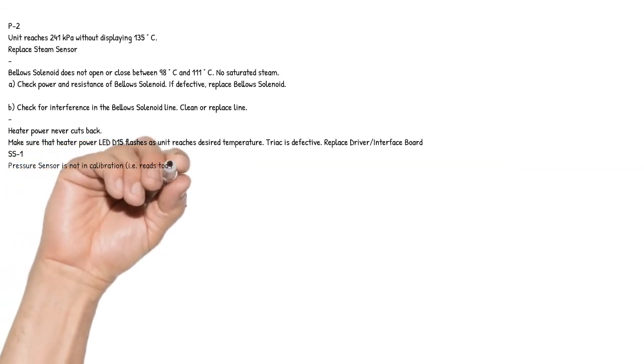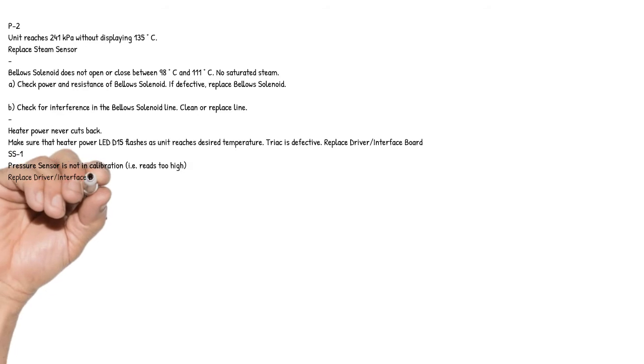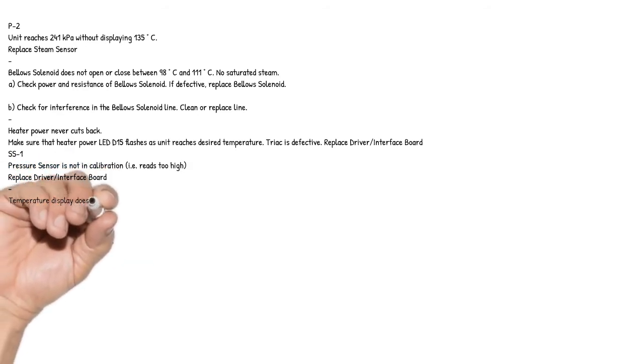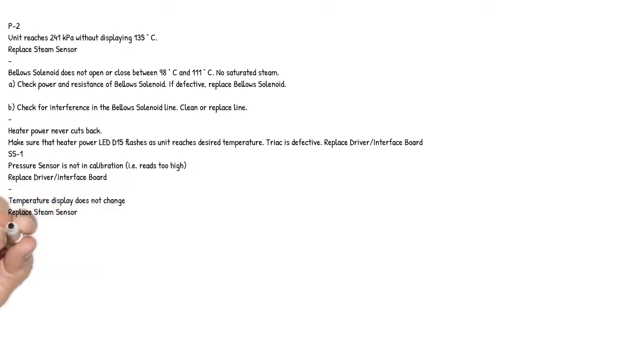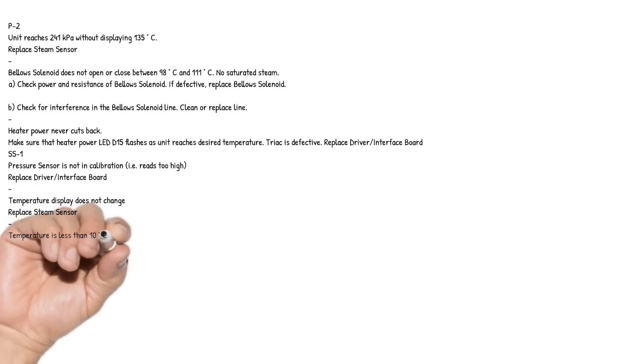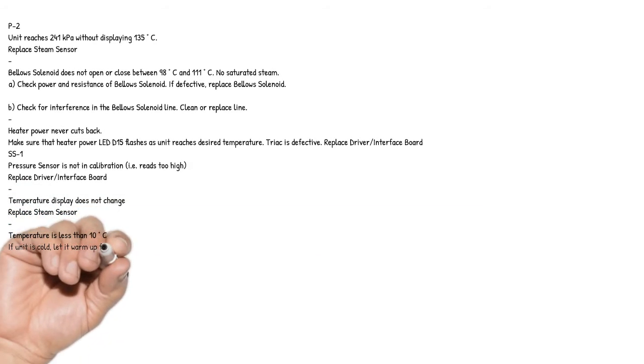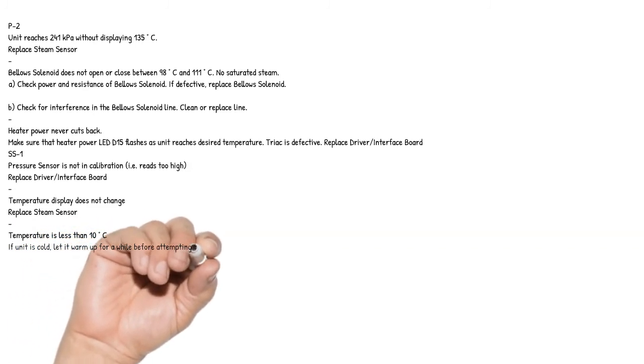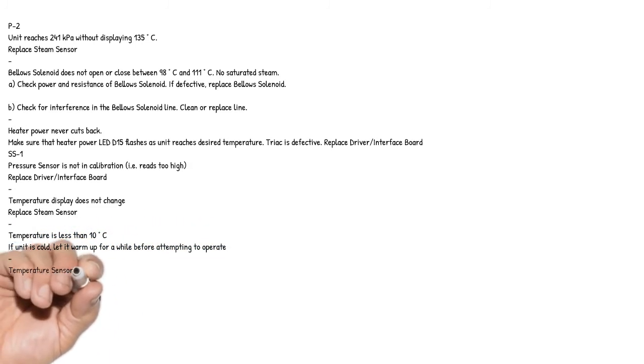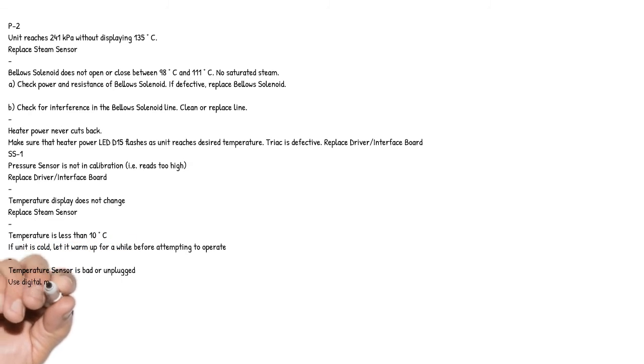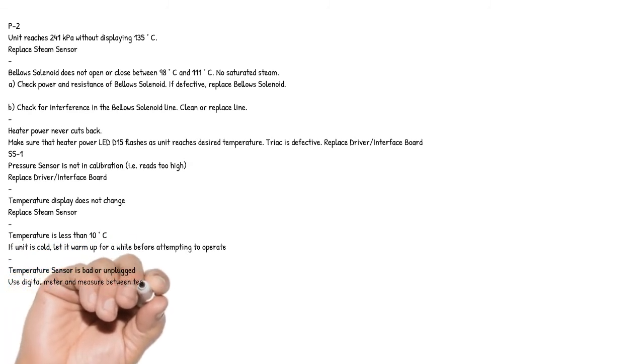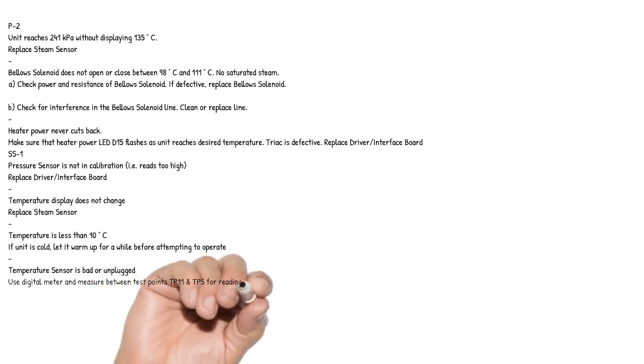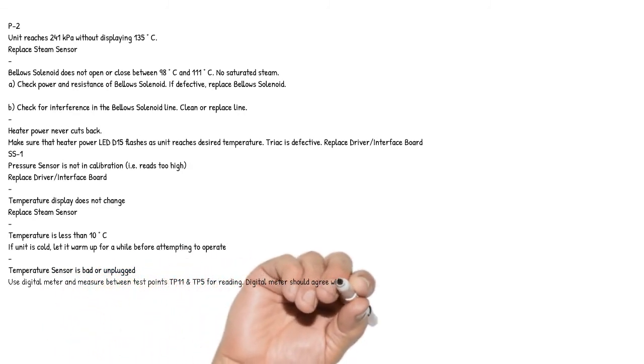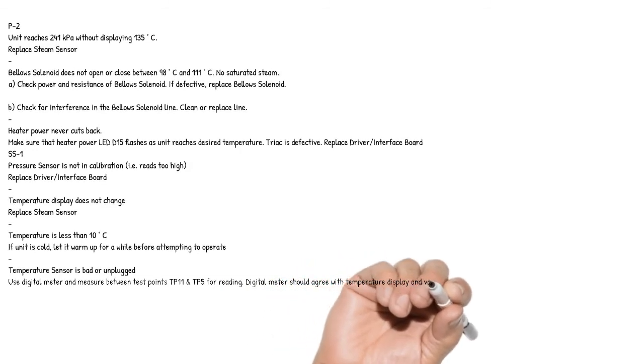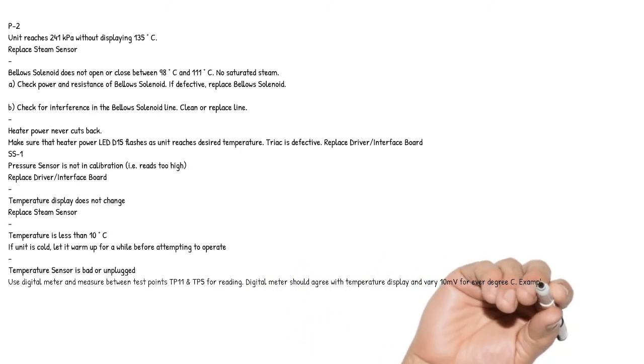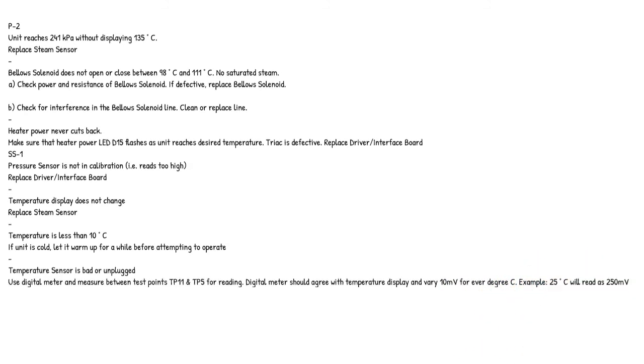SS1. Pressure sensor is not in calibration, i.e. reads too high. Replace driver/interface board. Temperature display does not change. Replace steam sensor. Temperature is less than 10 degrees Celsius. If unit is cold, let it warm up for a while before attempting to operate. Temperature sensor is bad or unplugged. Use digital meter and measure between test points TP11 and TP5 for reading. Digital meter should agree with temperature display and vary 10 millivolts for every degree Celsius. Example, 25 degrees Celsius will read as 250 millivolts.